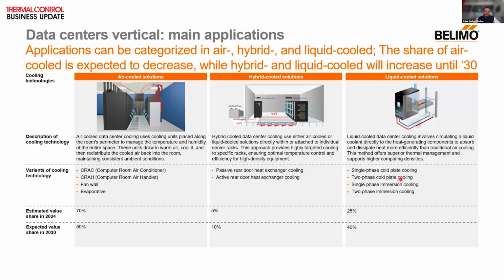So I'll quickly go through the summary. We have spoken about broadly air-cooled solutions, hybrid cooled, which has both air and liquid cooling, and then 100% liquid cooling. Each has its place in today's market, had its place in yesterday's market, and will have its place in tomorrow's market. When it comes to air cooled, we have CRAC units, fan wall units, evaporators, all these things. When it comes to hybrid cooling, we have passive rear door coolers or active rear door coolers. And in liquid cooling, we have single phase, two phase, or immersion cooling. So these are the available methods in the industry for data center cooling.